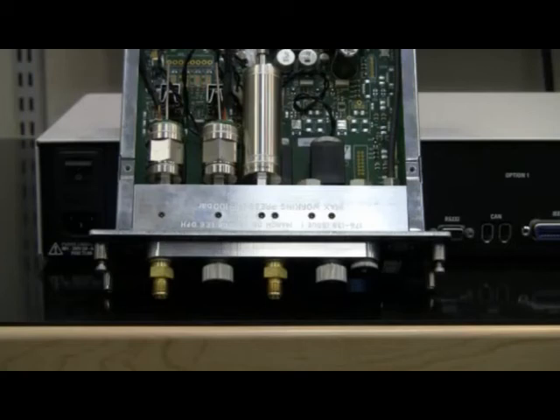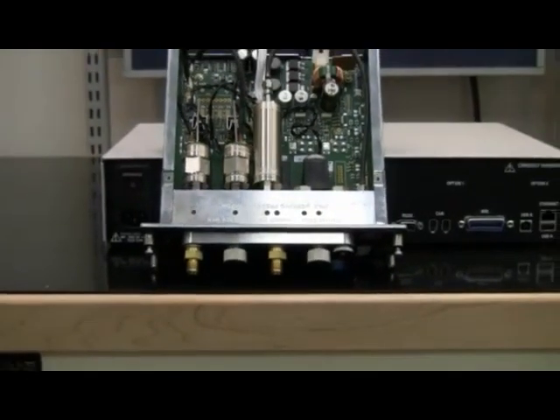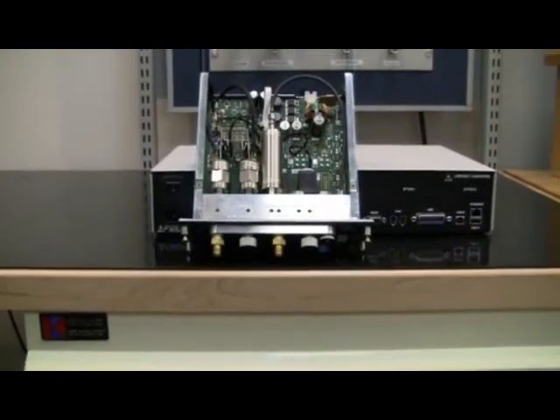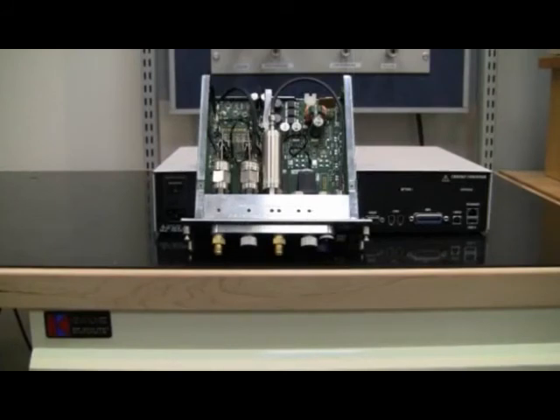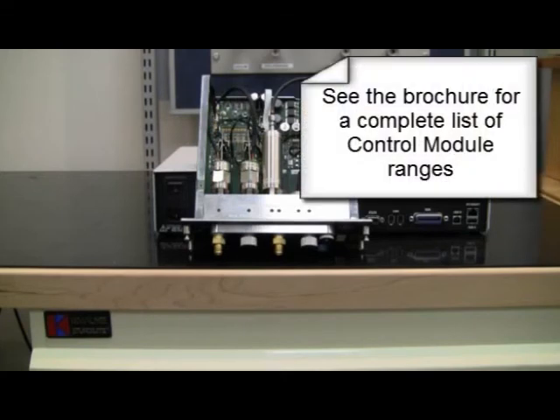A spare module on the shelf completely eliminates downtime. Since the pulse width modulated control valves are matched to the specific control module pressure range, optimal pressure control speed and stability is assured when changing control module ranges. A variety of control module ranges are available, from as low as 10 inches of water full scale or 25 millibar, to as high as 3000 psi full scale or 210 bar, providing maximum flexibility and rangeability in a single PACE 5000.